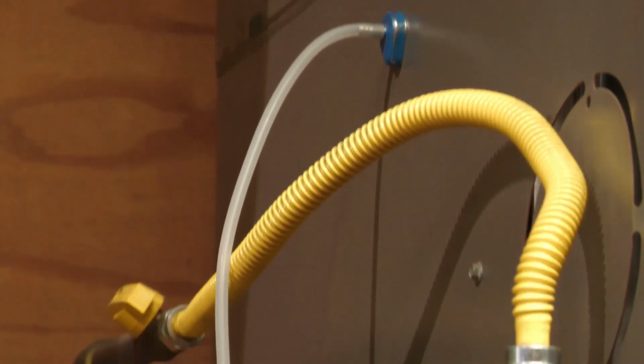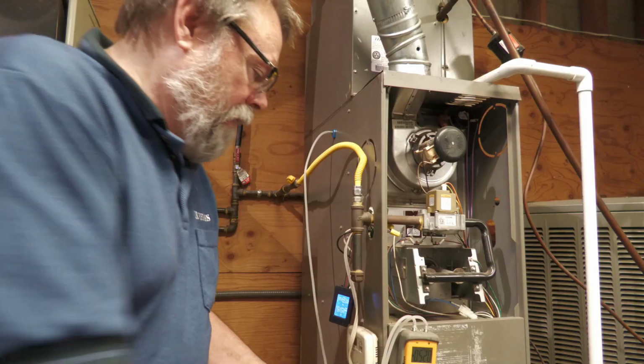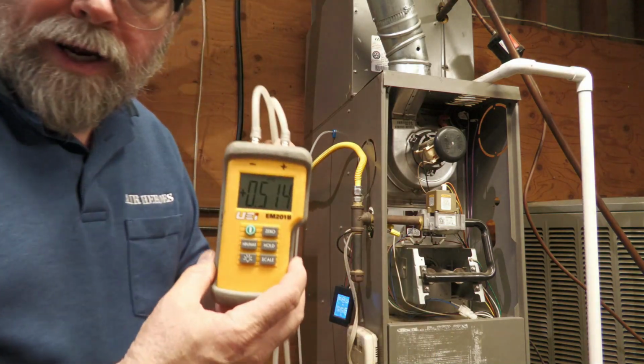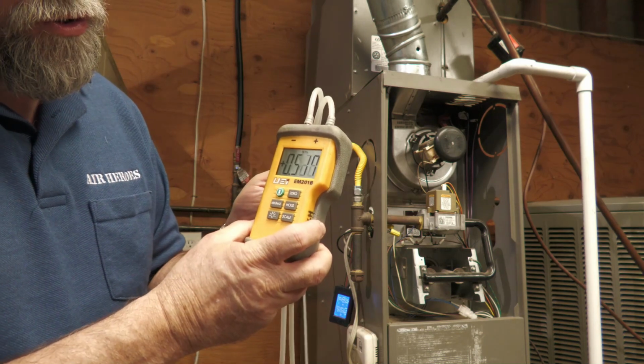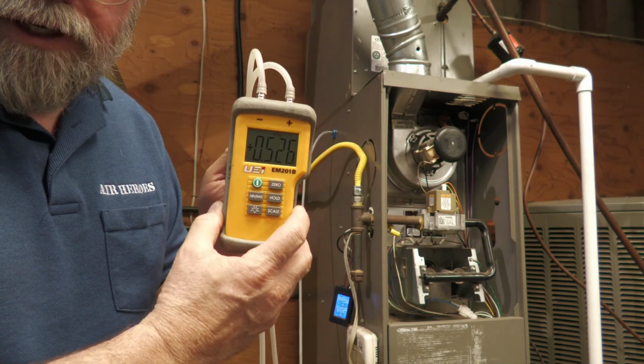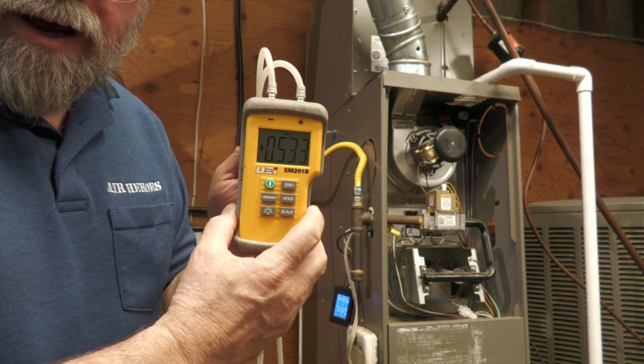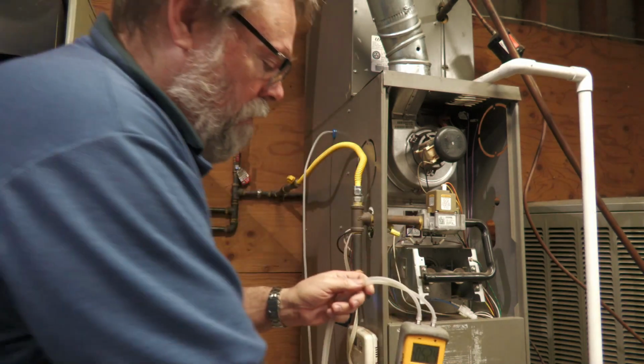That's not the maximum. So that being said, the way they rated SEER, or the way they rated the EER when they measured these partial loads, they used a static pressure of 0.1 inch for the piece of equipment when they measured all this stuff. The problem with that is almost all equipment out there that's manufactured for residential is at 0.5 inches of static, so a half inch of static. What is static pressure? That's the amount of resistance in the ductwork and in the whole system that will determine how much airflow we can actually move through the unit, or how many watts that's actually going to consume, because it takes more energy if we got to move more air.